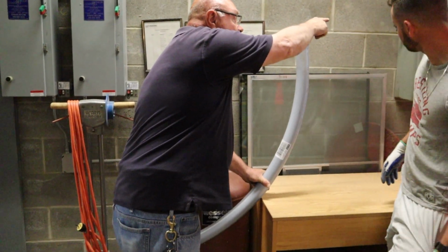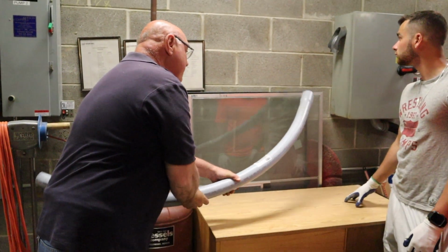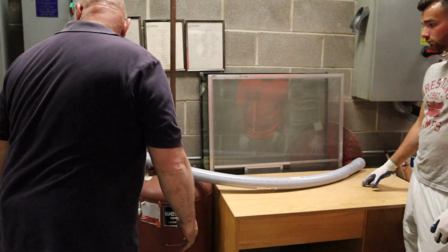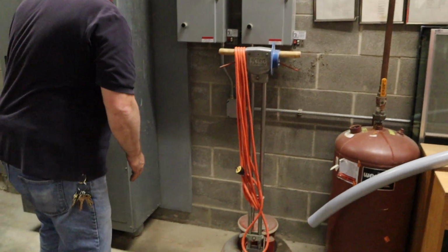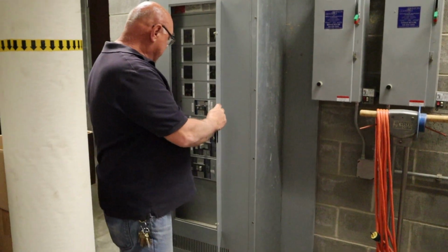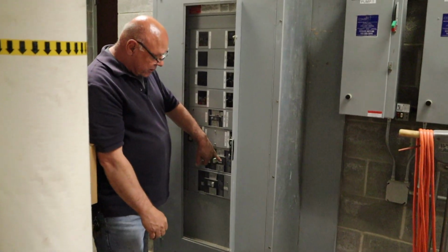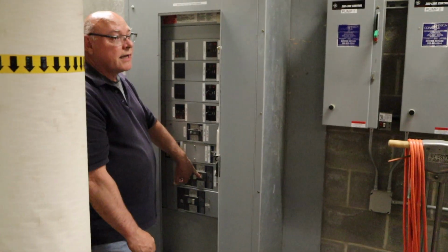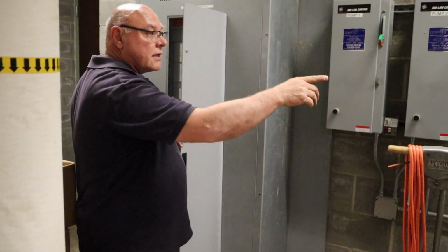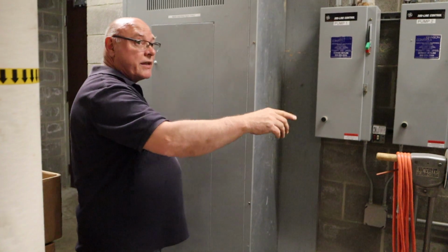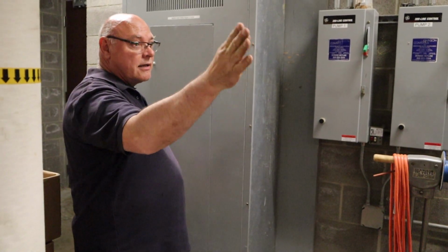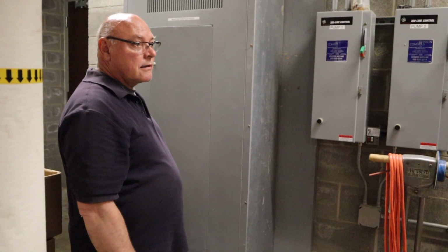This is our 90 coming up into our box for our main power. We're actually going to drill a hole in here and pick up our power from this 200 amp circuit breaker, so that's going to power that whole unit, and then we'll take power off of that and also send it outside to our condensing unit.